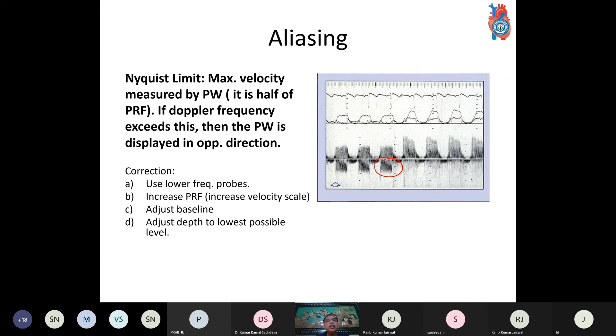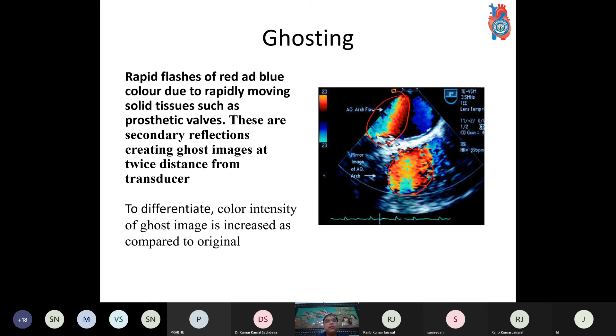Then comes ghosting. The same issue of aliasing, when it happens in color Doppler, is called ghosting. The rapid flashes of red and blue color are due to rapidly moving solid tissues such as prosthetic valves. These are secondary reflections creating ghost images at twice the distance from the transducer. So the same image is reflected as a mirror image because of the aliasing, and this is basically a color Doppler mirror artifact. To differentiate it, the intensity of the ghost image is increased as compared to the original.